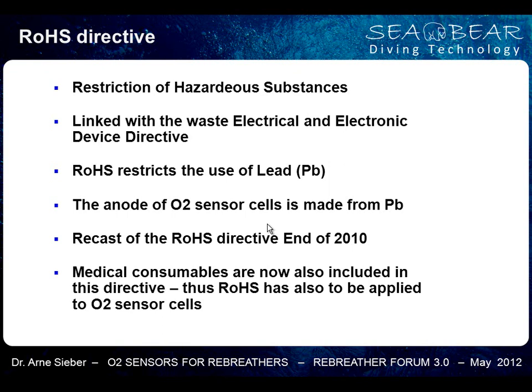There is this so-called RoHS directive, and I think it's worth that I talk 2 minutes about that. This RoHS directive is about a restriction of hazardous substances, and it's linked to the waste of electrical and electronic devices. This directive restricts the use of lead, and as I just explained to you before, lead is the material that we use in the sensor for the anode. So there was a recast of the RoHS directive in 2010, and this says now that medical consumables are now also included in this directive, and that it has to apply to oxygen sensor cells.